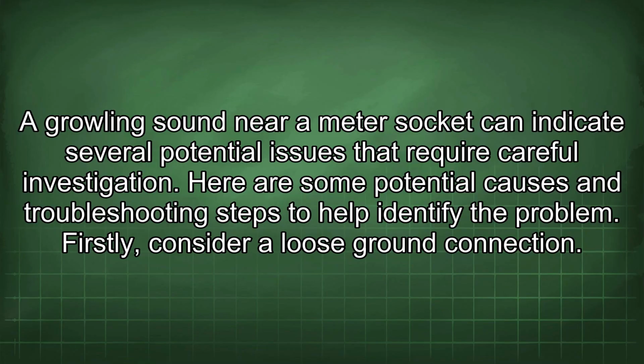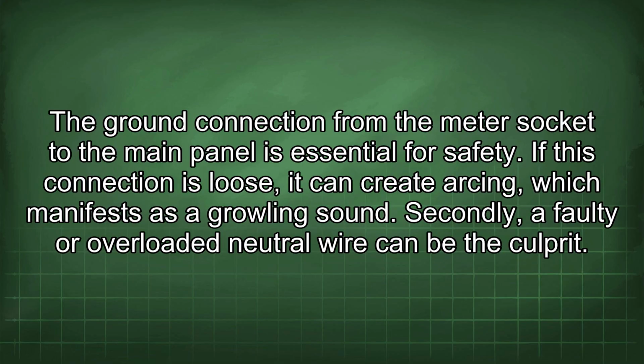A growling sound near a meter socket can indicate several potential issues that require careful investigation. Here are some potential causes and troubleshooting steps to help identify the problem. Firstly, consider a loose ground connection. The ground connection from the meter socket to the main panel is essential for safety. If this connection is loose, it can create arcing, which manifests as a growling sound.